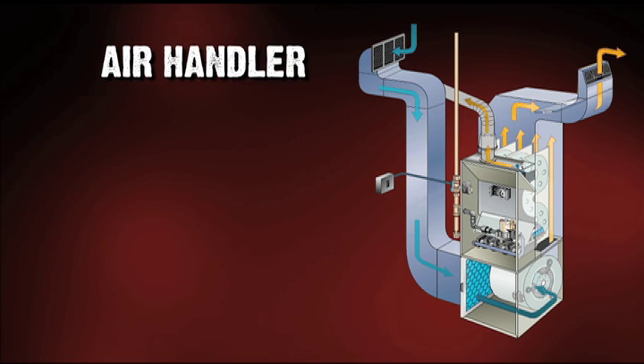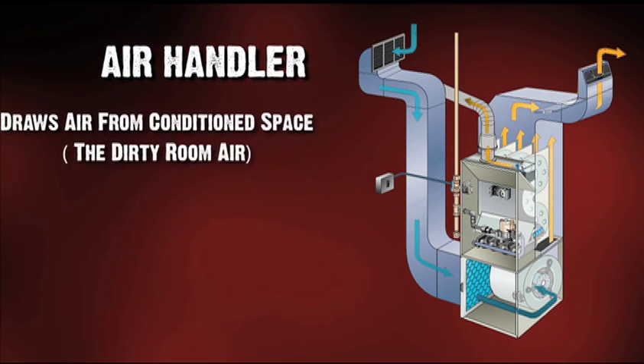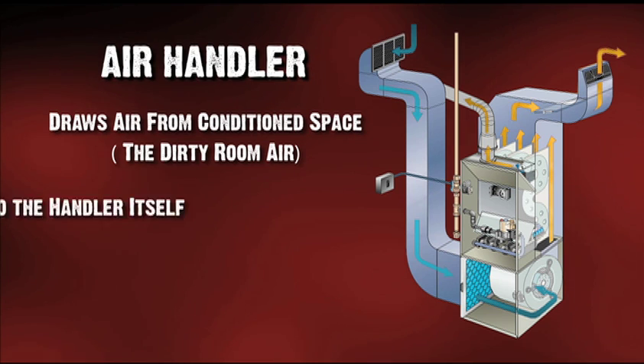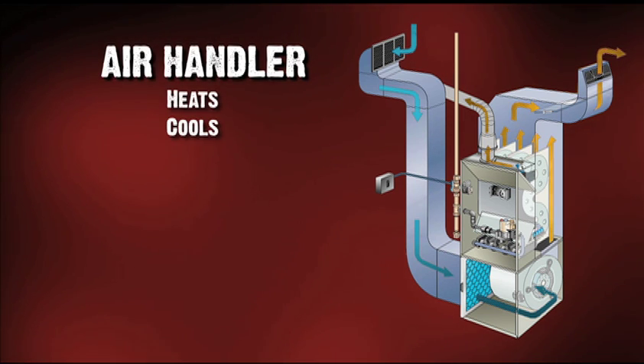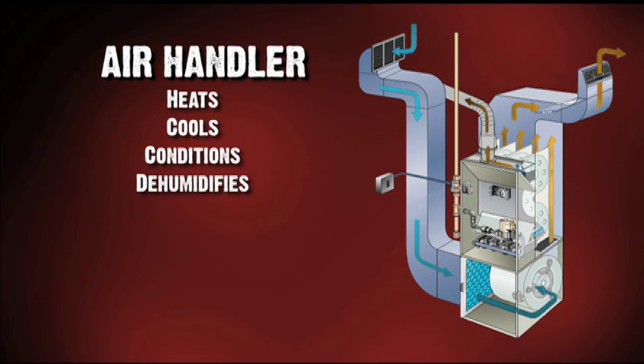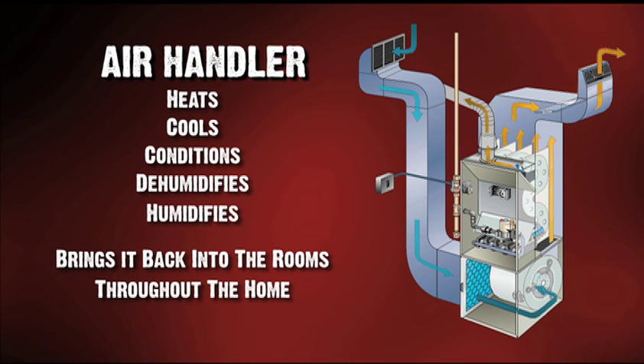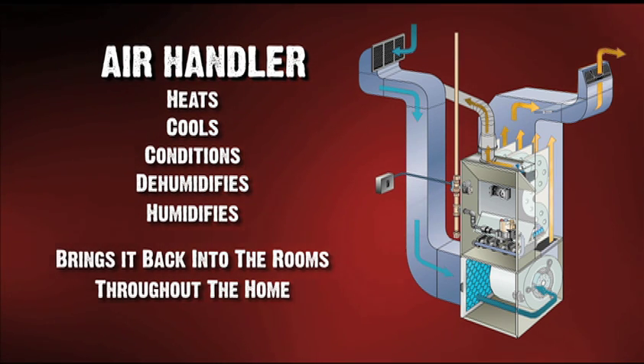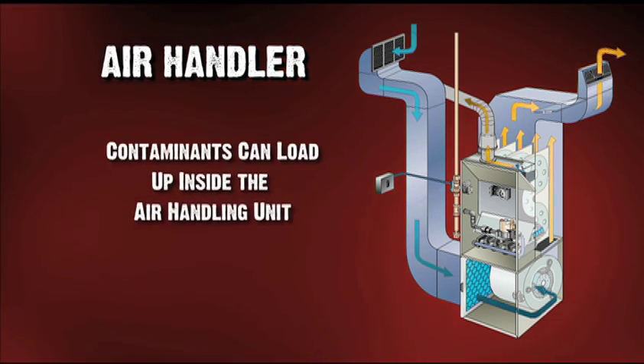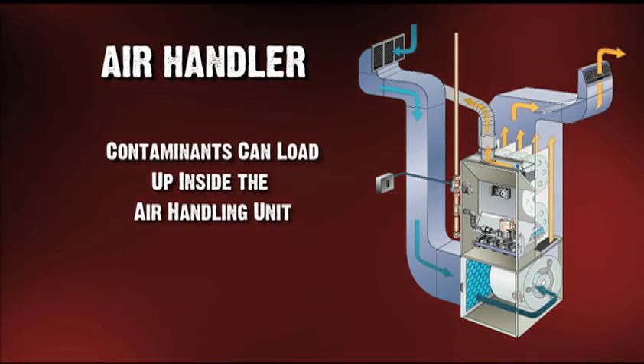Next, we're moving on to the cleaning of the air handler. The air handler can be located in attics, crawl spaces, or even basements in different parts of the country. What the air handler does is it draws air from the conditioned space, the dirty room air, brings it to the handler itself and heats it, cools it, conditions it, dehumidifies it, humidifies it, and brings it back into the rooms throughout the home. Because of that, all of the contaminants can load up in this air handling unit, and that's why it's important to make sure you topically clean the air handler unit as well.